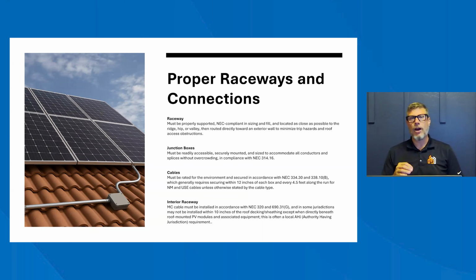Most places don't allow your raceway or your MC cable within 10 inches of roof sheathing, unless it's directly underneath the panel array. So if it's within 10 inches of the roof, any types of repairs run the risk of causing damage if it gets struck. If it's underneath the array, the chances are pretty slim that you're going to have a repair right there that's going to cause damage.